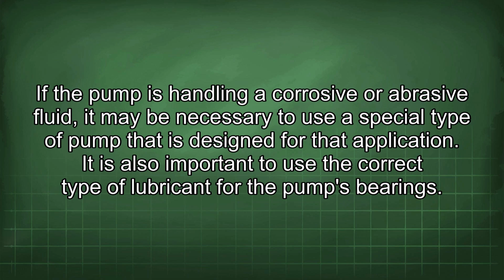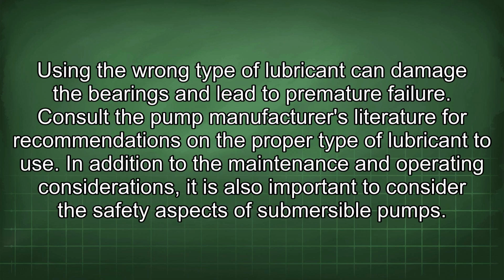It is also important to use the correct type of lubricant for the pump's bearings. Using the wrong type of lubricant can damage the bearings and lead to premature failure. Consult the pump manufacturer's literature for recommendations on the proper type of lubricant to use.